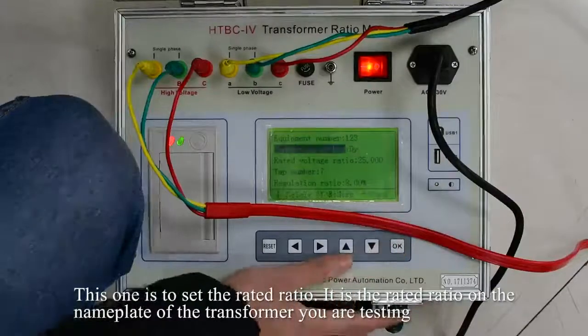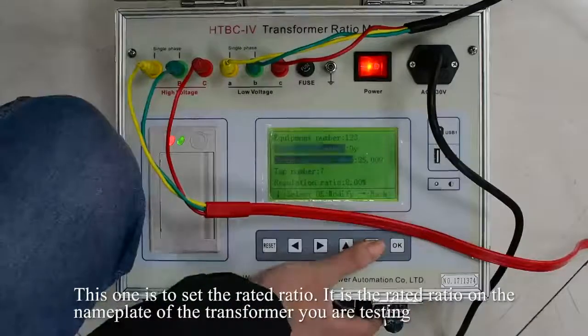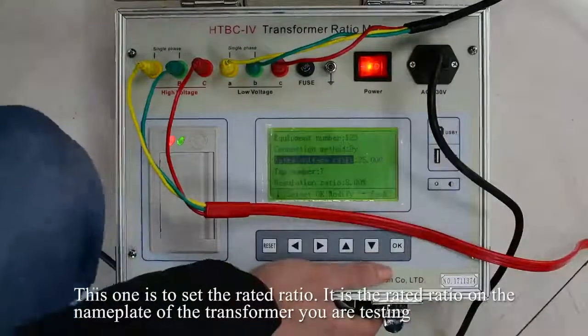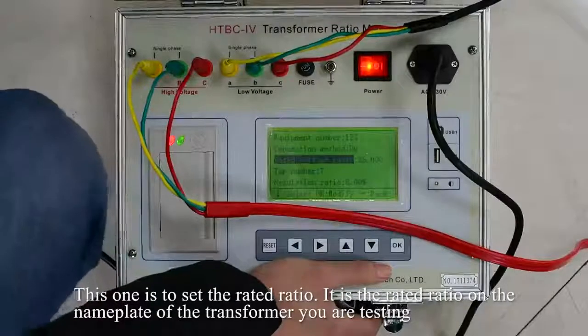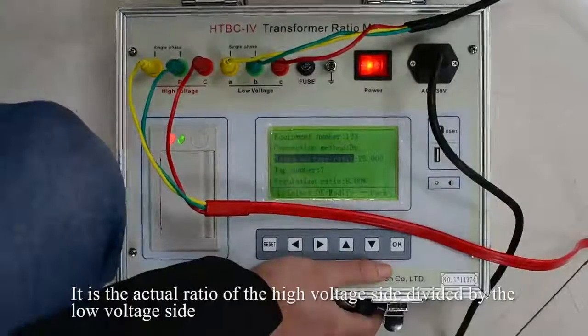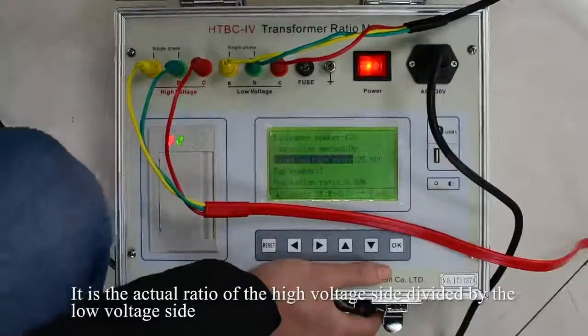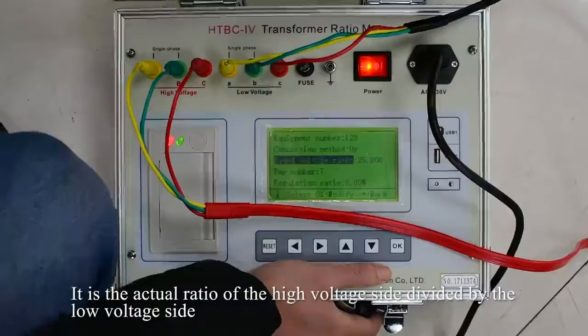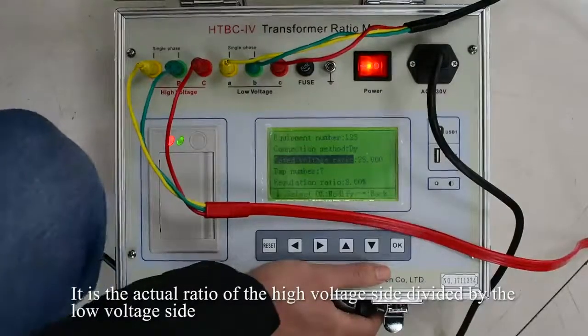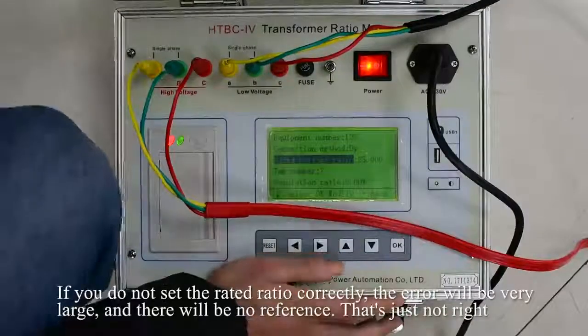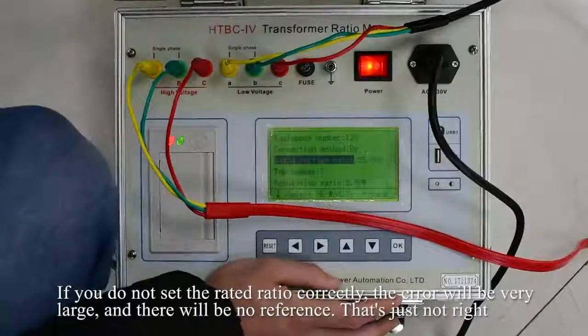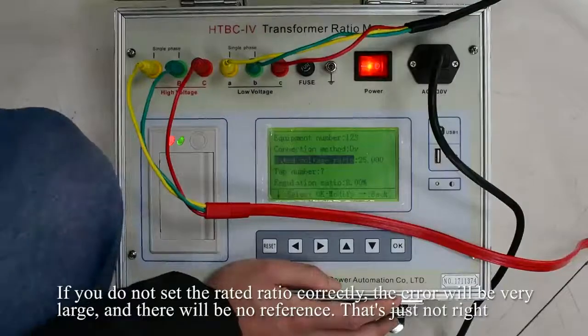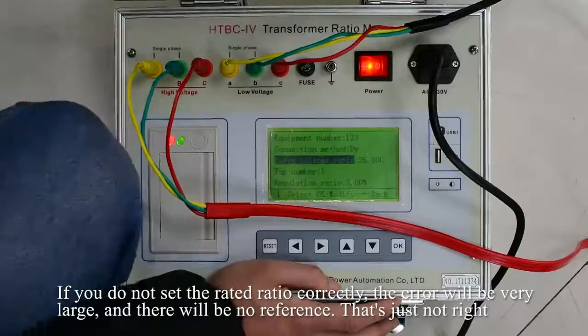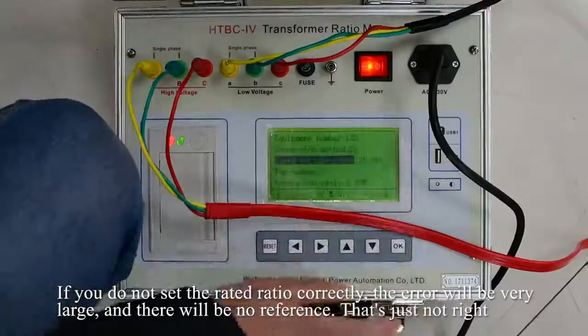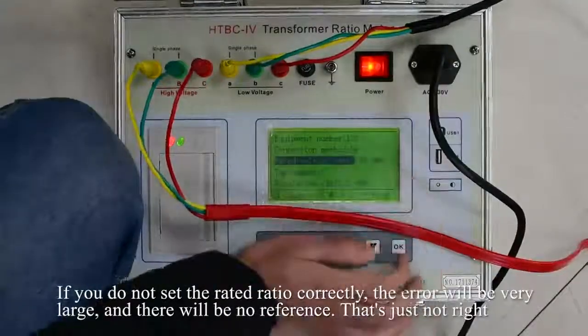This one is to set the rated ratio. It is the rated ratio on the nameplate of the transformer you are testing. It is the actual ratio of the high voltage side divided by the low voltage side. If you do not set the rated ratio correctly, the error will be very large and there will be no reference. That's just not right.